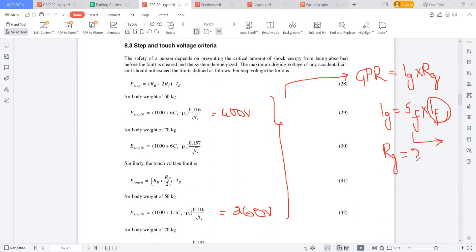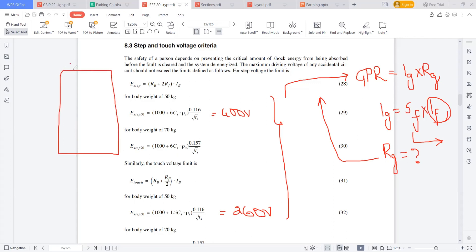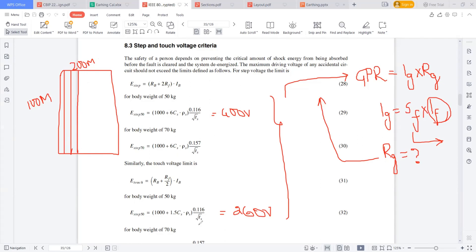To calculate the grid resistance, you have to form the grid first. How to form the grid? Generally it is a kind of a trial and error scheme. Suppose this is my substation — I am having a 200 meters by 100 meters land for my substation. I will place the conductors like this — a trial and error case. I am placing the conductors.